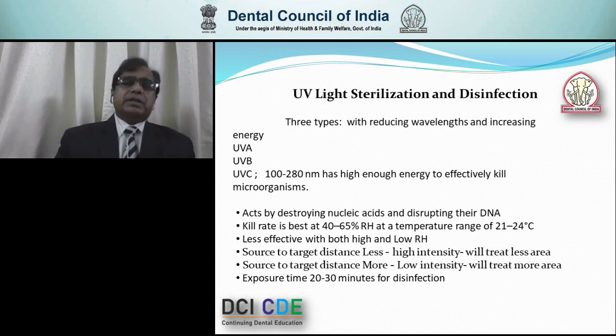If the source to target distance is less, the intensity is high, and it will treat a smaller area. If the source to target distance is more, the intensity will be low, but it will treat more area. So if you are going to choose UV light sterilization or disinfection, you have to calculate the area you have to disinfect, and buy accordingly. Exposure time is 20 to 30 minutes for disinfection.